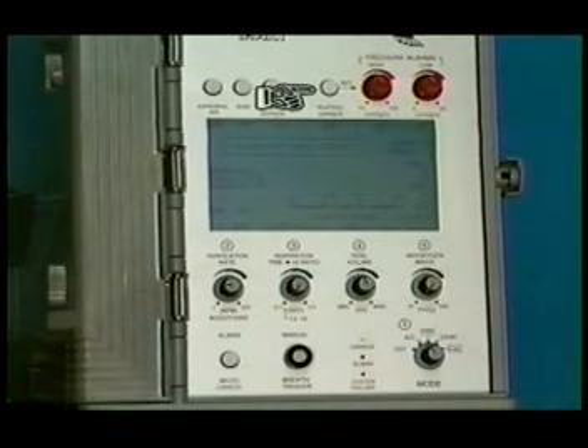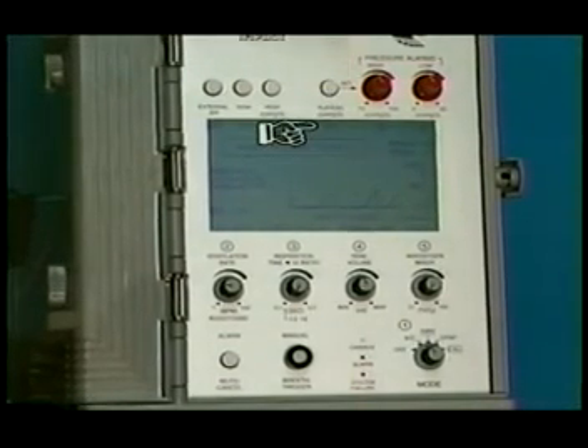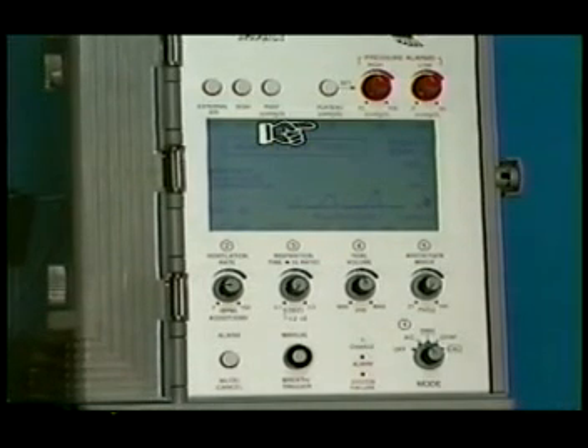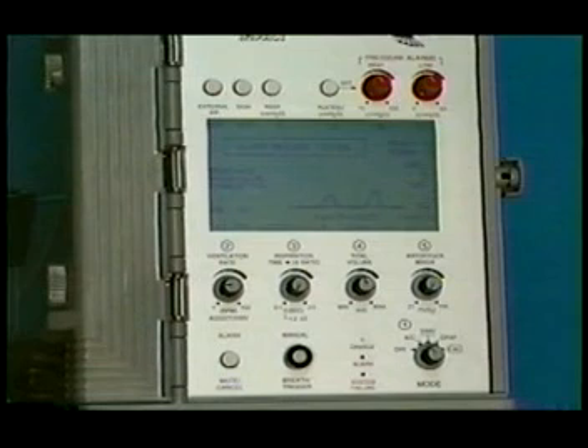The pressure plateau off-on push-button switch has a default value of off. When pressed to on, the plateau value is automatically referenced 10 centimeters of water less than the high-pressure alarm peak inspiratory pressure relief control set point. The plateau range is 5 to 90 centimeters of water, and its value is displayed in the LCD beneath the push-button switch. Pressure plateau is disabled when sigh is on.